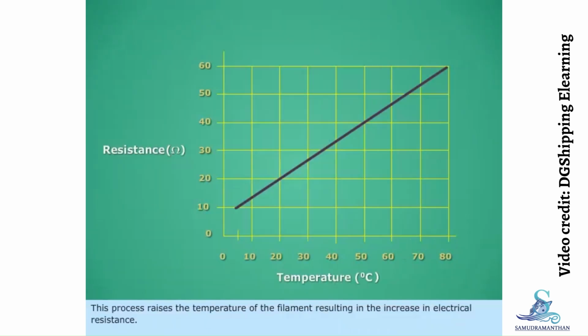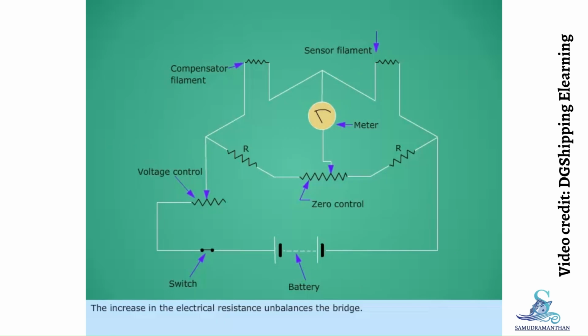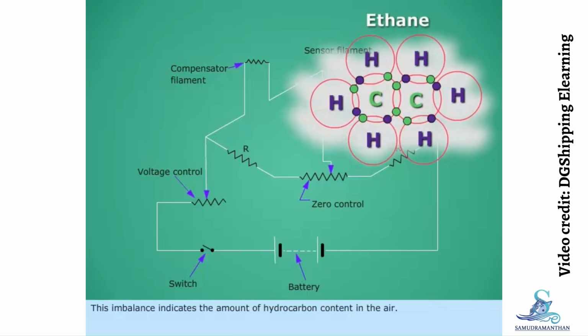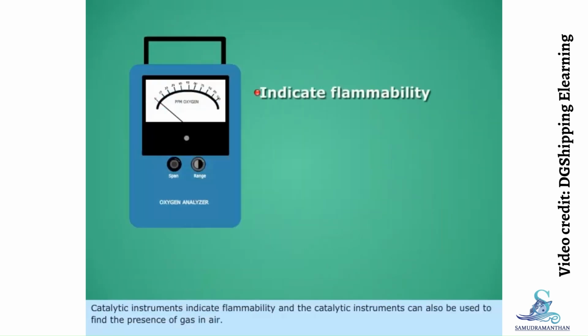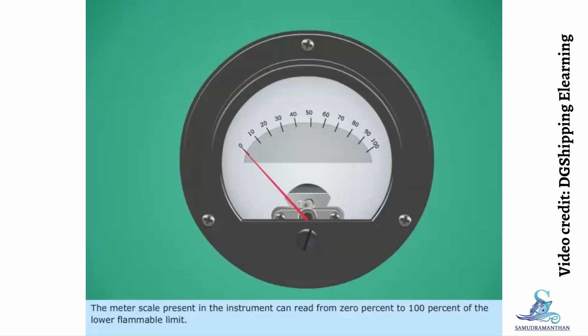This process raises the temperature of the filament, resulting in the increase in electrical resistance. The increase in the electrical resistance unbalances the bridge. This imbalance indicates the amount of hydrocarbon content in the air. Catalytic instruments indicate flammability, and they can also be used to find the presence of gas in air. The meter scale present in the instrument can read from 0% to 100% of the lower flammable limit.